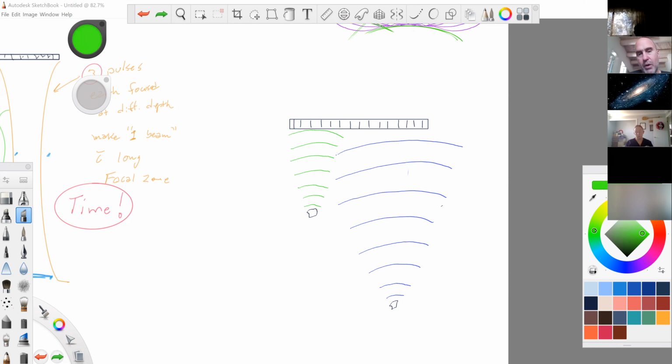On the first echo, on the first object, the elements that are going to be stimulated are these. All of those elements are going to hear that object, if that makes sense to you. They're going to hear it. And in fact, there's a little bit of a timing difference. You could see by the curvature in this wave that this one is going to hear it first.